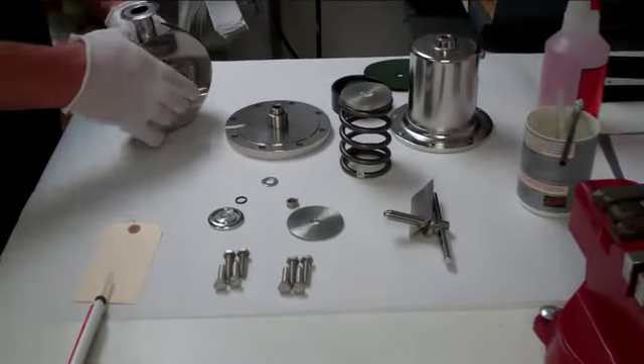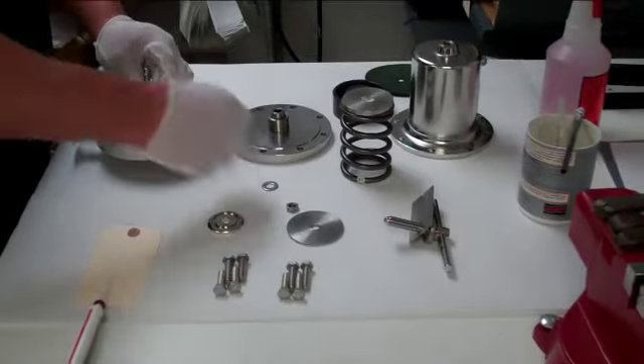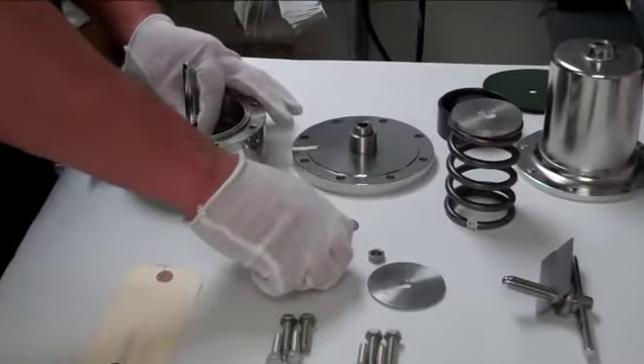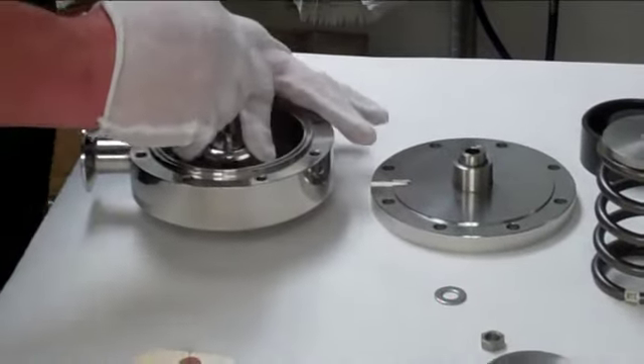First, take your body with the flange facing you and pull your stem plug assembly through the body. Now, place on your first washer and the lower diaphragm plate with the grooves facing upward.